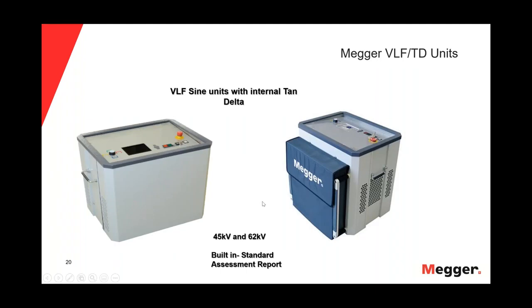What we have here is our product list for VLF sine units with internal tan delta. So here we have a 45 kV unit and a 62 kV unit. All of these units have a built-in standard assessment reporting already. So these units not only have the VLF technology with the sine wave, they also have the built-in tan delta. So no need for an external type connection or extra connections to be able to have your tan delta values. And all of the reporting that we just went over is also built into the assessment report.